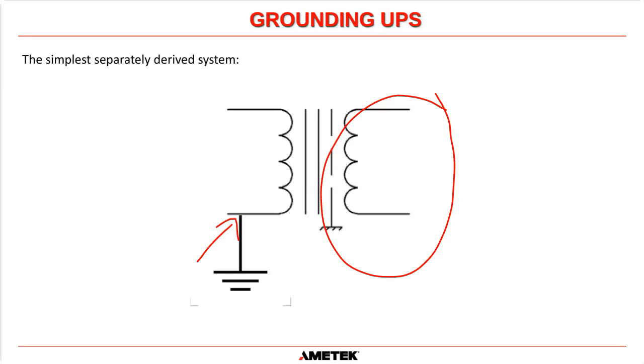And what that means is, in this drawing here, to comply with electrical code, what you would then have to do is connect an additional ground. Now you can connect that ground directly to this ground over here and do that. But if you want to comply on a separately derived system, you have to connect the neutral on the secondary side of that transformer to ground to maintain that connection.